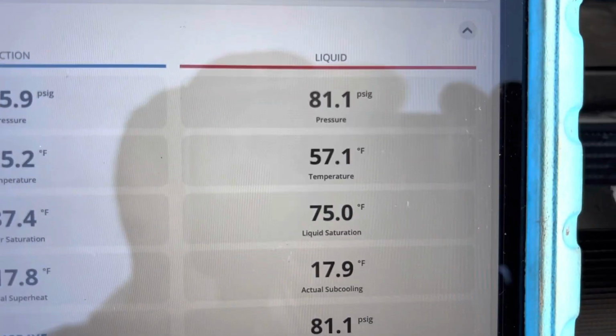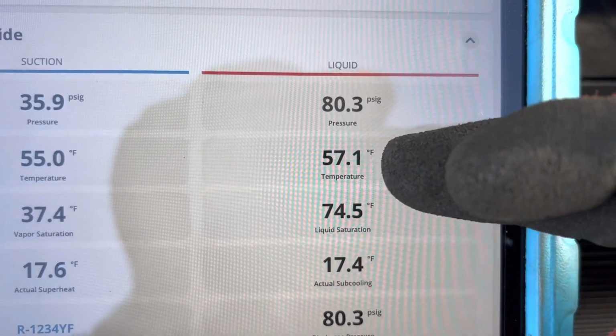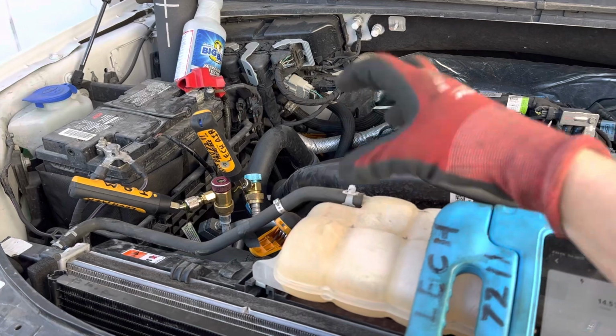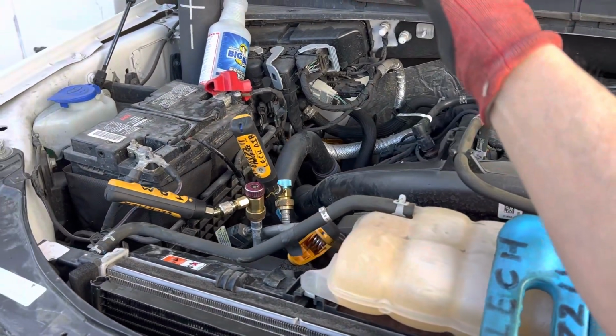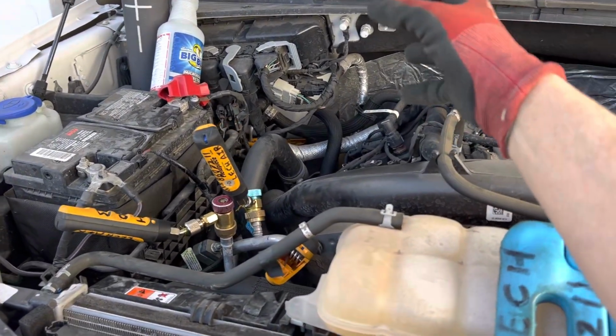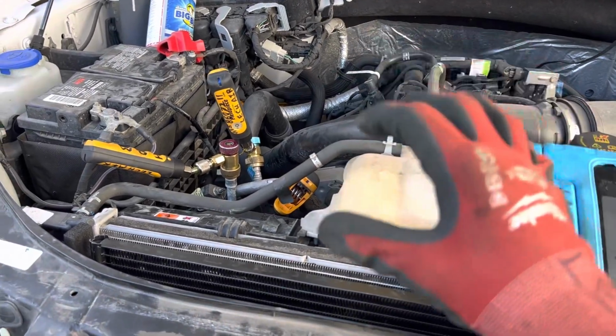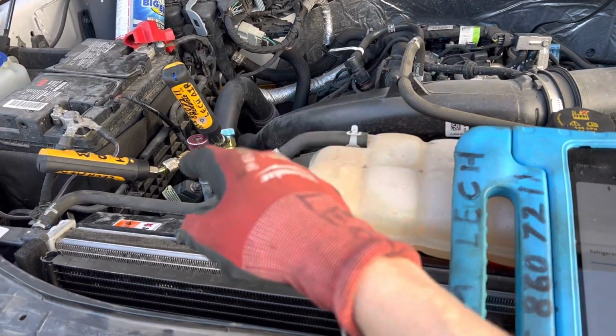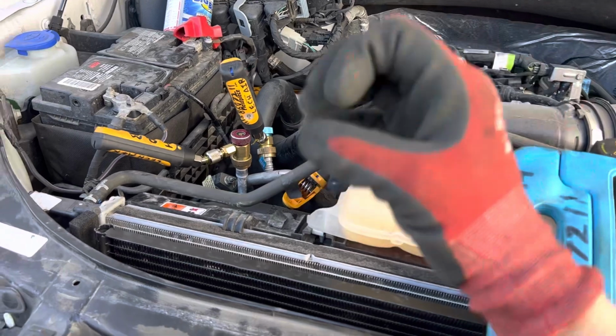57 degrees. Right here. So it absorbed some energy out of the liquid refrigerant, and it gave it a little bit more subcooling, so there's a little more potential energy per pound of refrigerant flowing to the expansion valve to absorb more heat out of the evaporator. By using that internal heat exchanger, it makes the system a little more efficient.